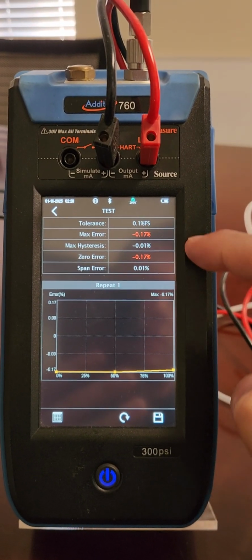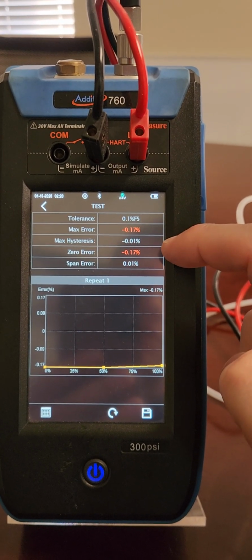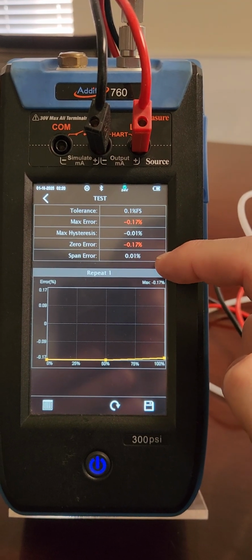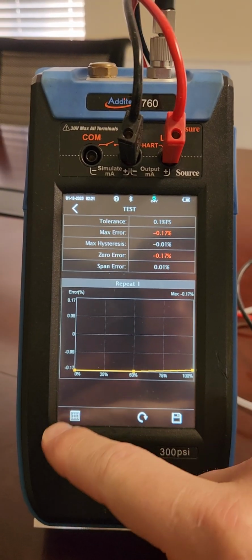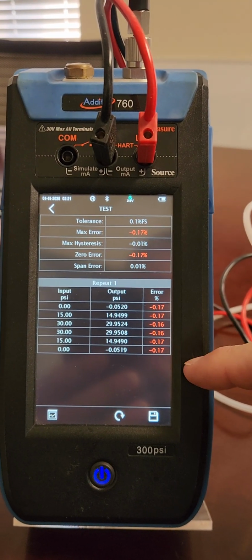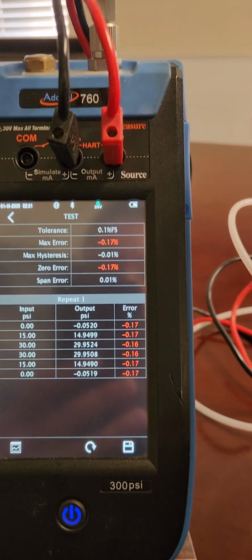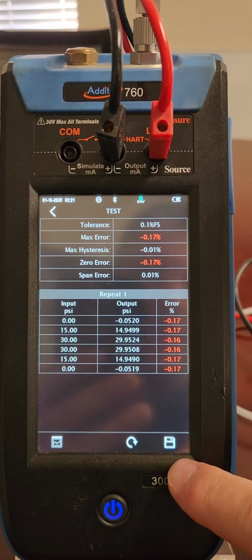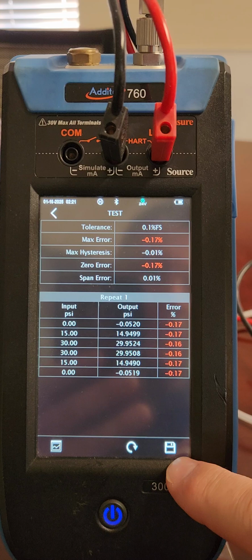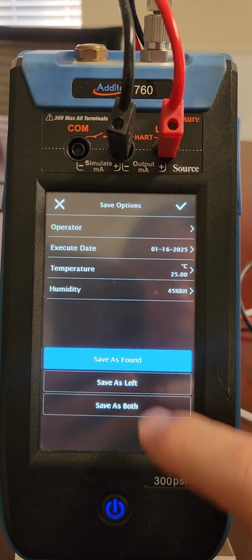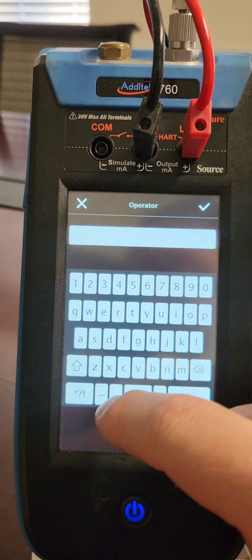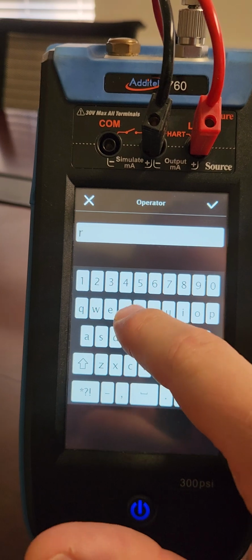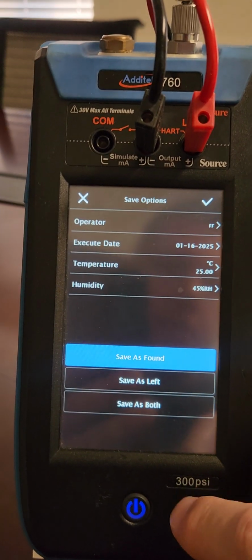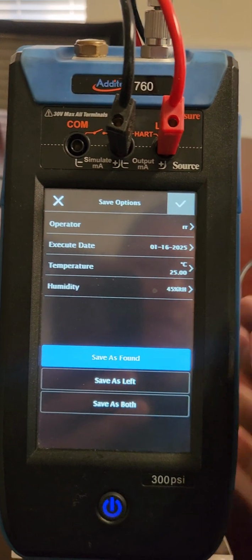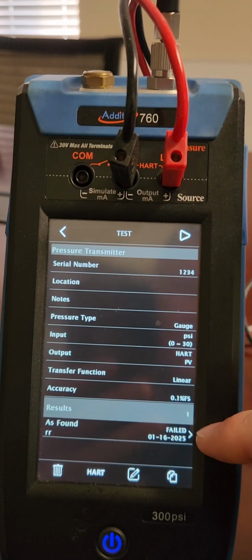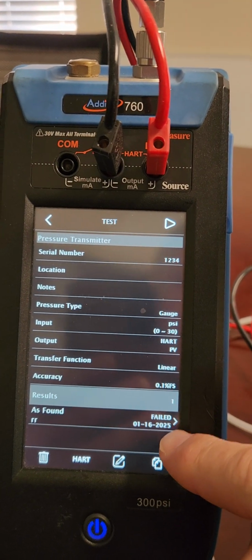Okay, so here's our test data. It shows a tolerance, max error, hysteresis, 0 error, and span error. If everything looks good, which obviously this data is not good, so we need to do some adjustments. So we can just hit save. Save as found, enter in the operator, and save as found, and it saves that data. And that's stored here under the test, and so here we have our test that we took today.